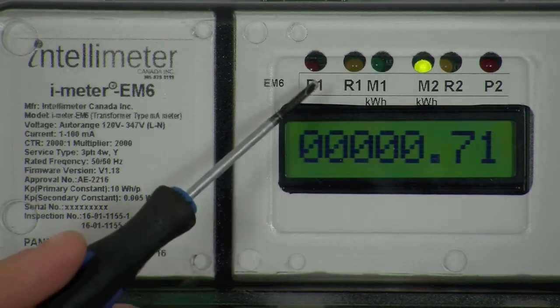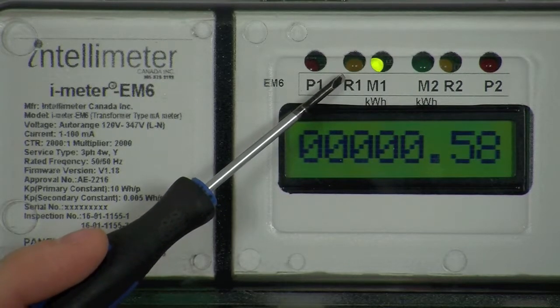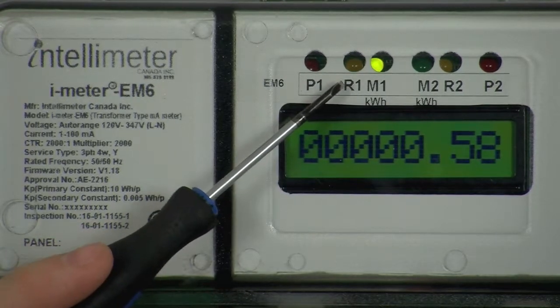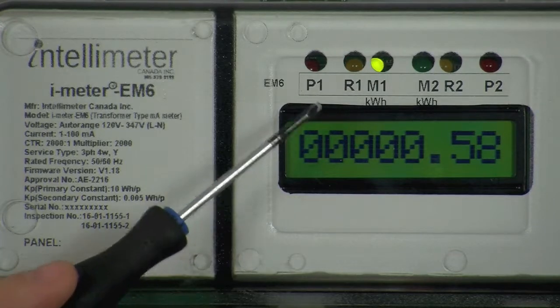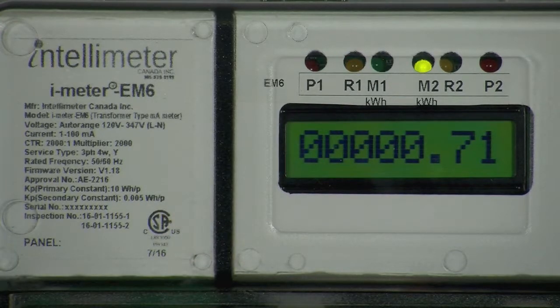As you can see, here we have a blinking amber light on R1. As I just mentioned, this tells us that there's a problem with the installation of one or more of the CTs for meter 1. We're going to start by checking CT1, making sure that the CT is not installed in the reverse direction. Remember that the arrow on the CT label must point in the same direction as current flow.